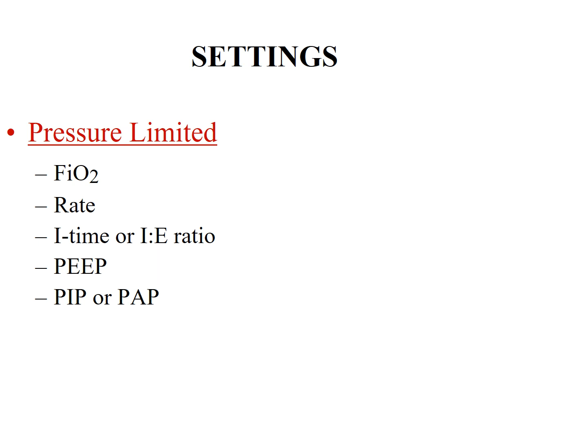Depending upon what you want to achieve, generally speaking, you need to have a good chest rise or an appropriate tidal volume, and this is for the pressure limited ventilation. So then we talked about the tidal volume around 6 to 8 ml per kilogram. But for those who have got white lungs, you would tend to keep tidal volume at the lower side because of the protective effect of low tidal volume in diseased lungs. So you would tend to keep a tidal volume of maybe 3 to 5, around 5 ml per kilogram in these cases. You just don't keep on increasing PEEP, you just keep an eye on what is happening with your tidal volumes as far as the pressure is concerned.